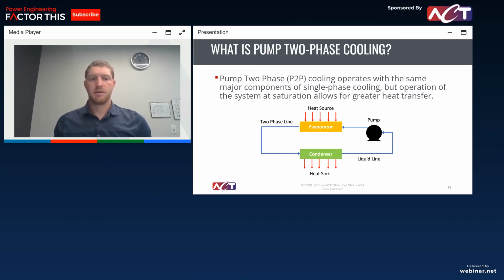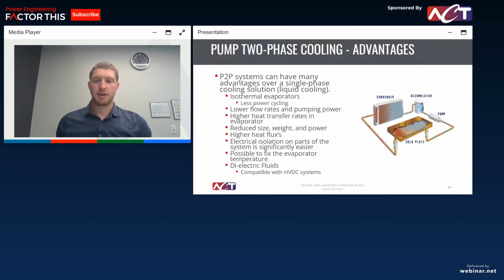So next, I'm going to talk about pump two-phase cooling. Pump two-phase cooling operates very similar to a single-phase cooling loop. You'll have an evaporator, a condenser, a pump, and oftentimes you'll have a reservoir or an accumulator as well. That's not pictured in this one here, but just like with loop thermosyphon, we're basically operating the system at saturation. So you have partially vapor, partially liquid running through your evaporator, and that's going to allow for a much greater heat transfer.